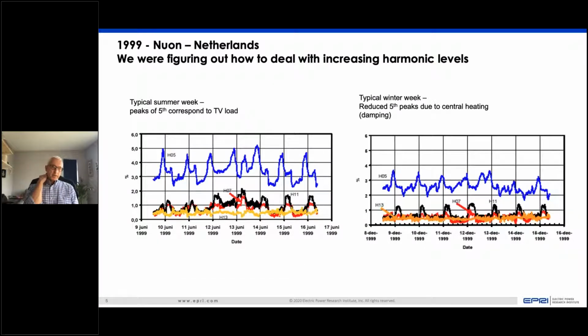And for the harmonics, I picked a study that was done by Nuon in the Netherlands back in the 1990s, a really important period of investigation and research into harmonic issues. This was a really interesting chart that Nuon came up with, looking at summer and winter conditions and harmonic distortion levels on the system. You can see on the chart on the left that in the summer, when there wasn't so much heating load, which provides damping of resonances, the harmonic levels were quite high, reaching over 4% at the 5th harmonic and over 5% voltage distortion during many periods. And the levels were really related to resonances created by capacitor banks on the grid.